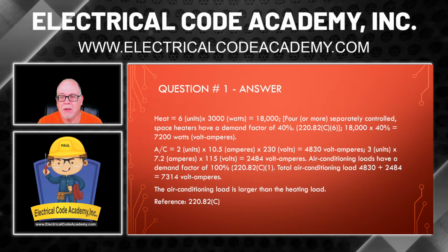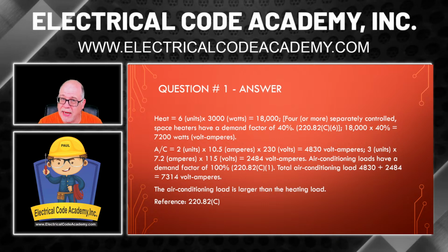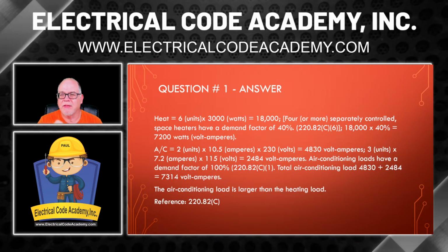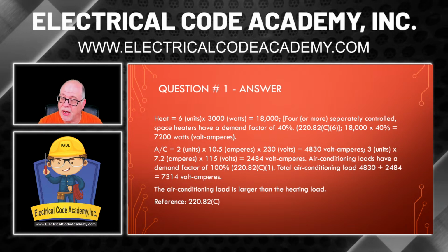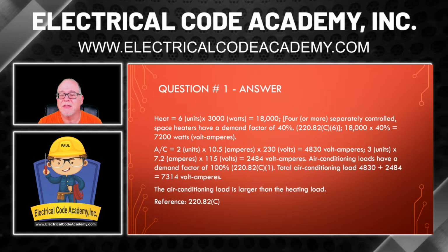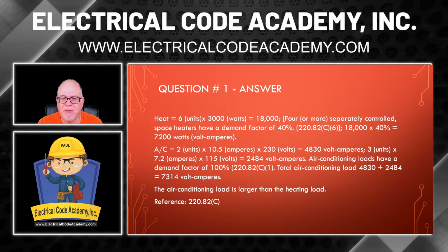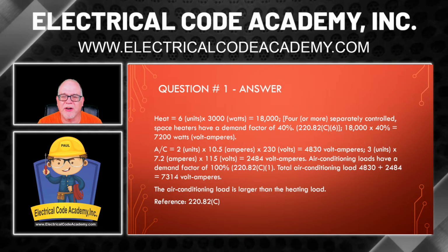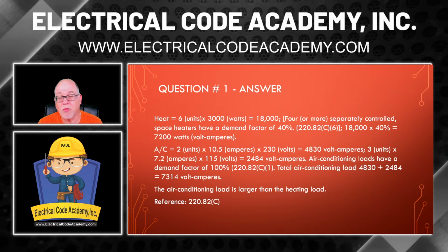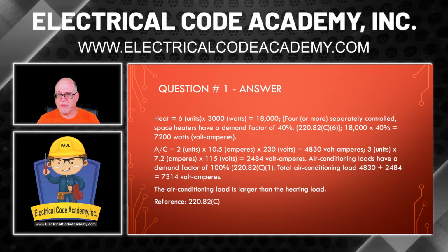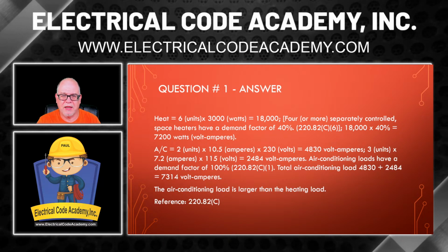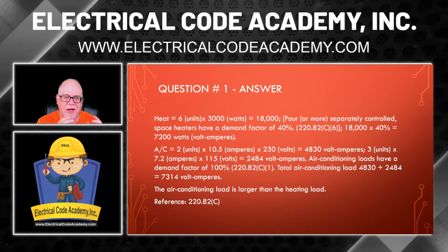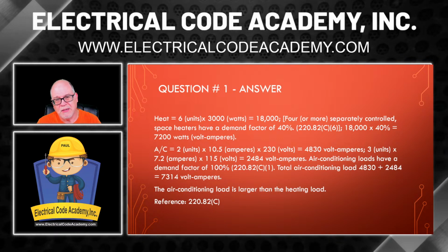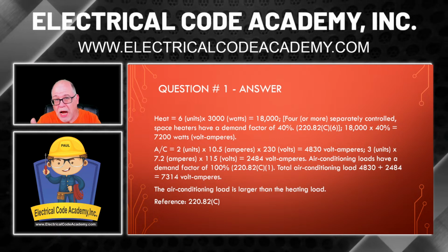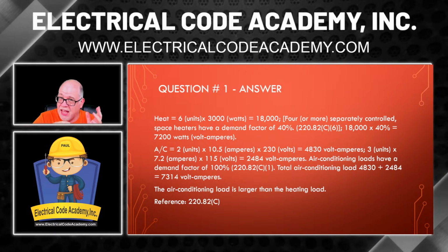Now let's do the 3 7.2 amp air conditioning units. That would be 3 times 7.2 times 115 volts. That is 2,484 volt amperes. Remember Ohm's law: in order to find VA, it's synonymous. We're just going amps times volts equals watts, and watts is synonymous with VA.